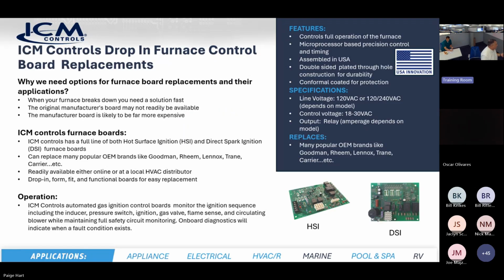So first of all, we'll talk about what we're doing here. We make drop-in furnace control board replacements. If you live in the Northeast, it's going to get cold, we're going to have heating. A lot of times that heating is natural gas, could be propane, could be other types of fuels, but something has to control that fire. You're going to create a fire, you've got to create heat somehow, and something's got to control that. There are other sources of heating devices, including geothermal, which uses heat from the ground, but we're going to talk today about more traditional style heating, like natural gas, which would run heaters in your residential homes, or boilers for hot water heating.